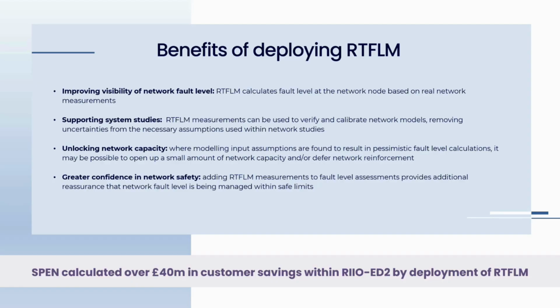Obviously, we can then use that to support the system studies. So we can use the measurements we obtained to verify and calibrate network models and help remove some of the uncertainties from the necessary assumptions that we use. Where modeling input assumptions are found to be a bit pessimistic in fault level calculations, it might be possible to open up a small amount of network capacity and/or defer network reinforcement.